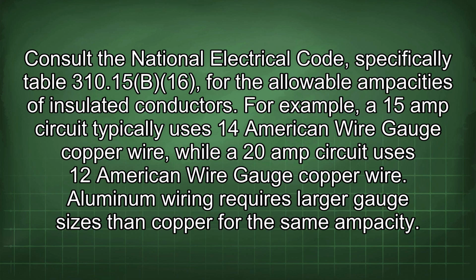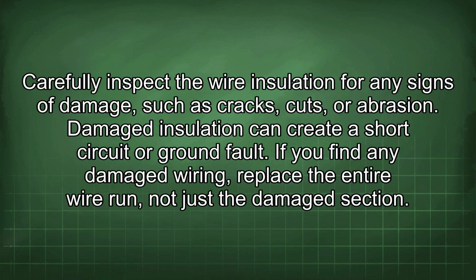Aluminum wiring requires larger gauge sizes than copper for the same ampacity. Carefully inspect the wire insulation for any signs of damage, such as cracks, cuts, or abrasion. Damaged insulation can create a short circuit or ground fault. If you find any damaged wiring, replace the entire wire run, not just the damaged section.